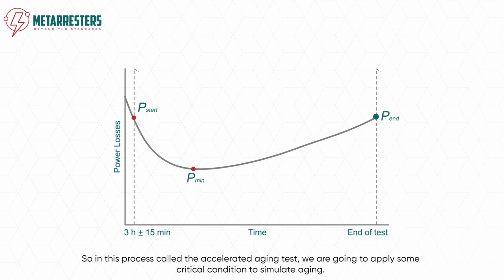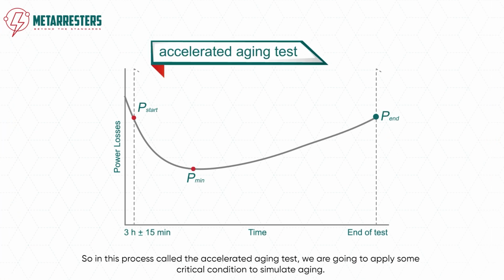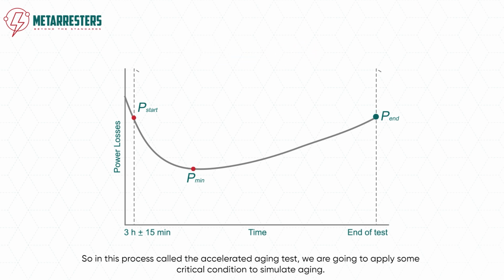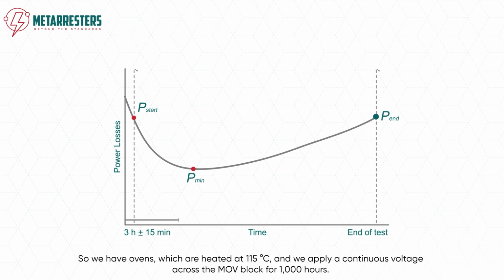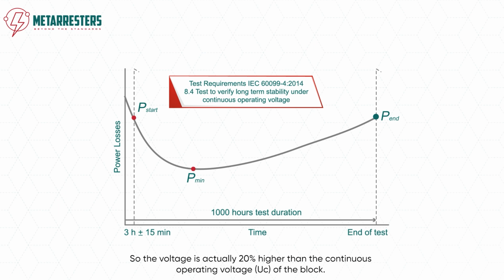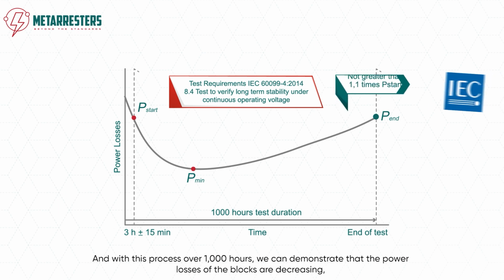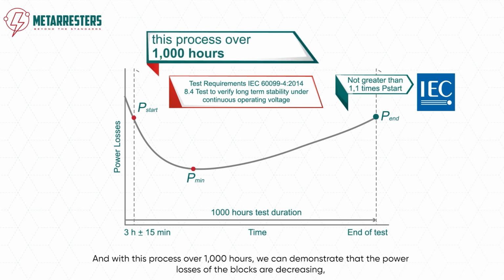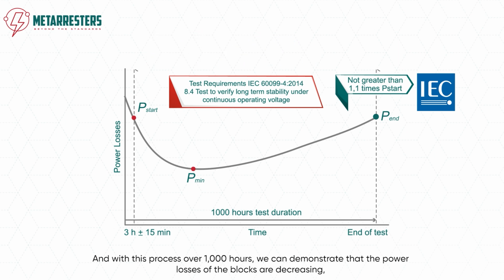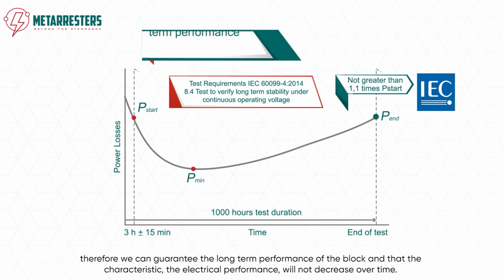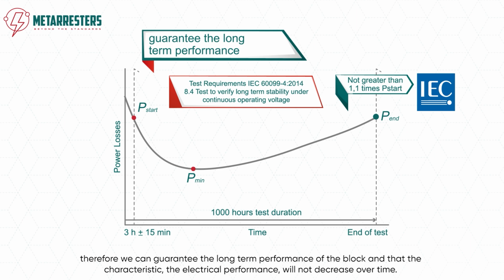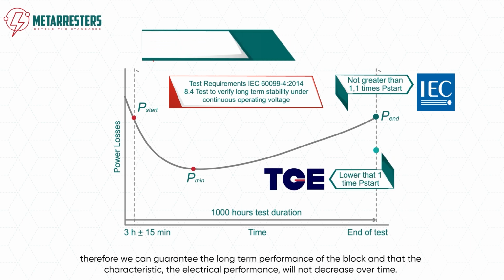So in this process called the accelerated aging test, we are going to apply some critical conditions to simulate aging. So we have ovens which are heated at 115 degrees Celsius, and we apply a continuous voltage across the MOV block for 1,000 hours. So the voltage is actually 20% higher than the continuous operating voltage of the block. And with this process over 1,000 hours, we can demonstrate that the power losses of the blocks are decreasing. Therefore, we can guarantee the long-term performance of the block and that the electrical characteristics will not decrease over time.